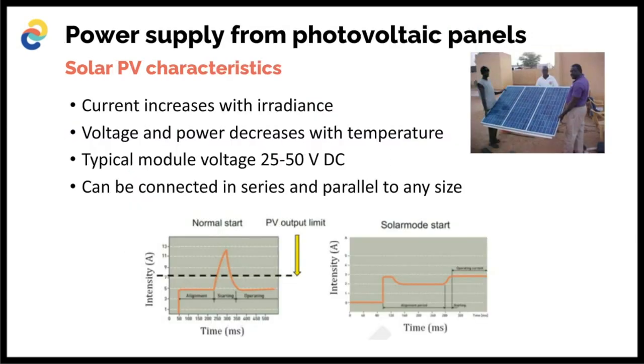The speciality about solar PV panels is that the current increases with irradiance, but as we have a limited amount of irradiance, the current cannot be unlimited. Typically we have a current of about 10 amps for such a PV panel, and the voltage is between 25 and 50 volts. But if you could construct a compressor that can, in an intelligent way, start up without too much inrush current, then it could work.